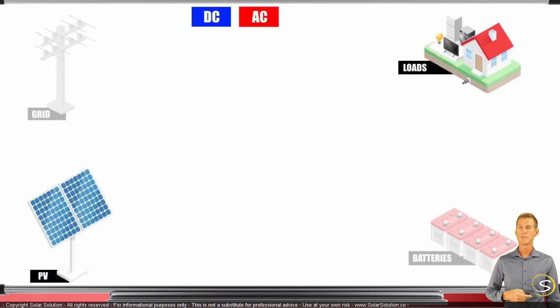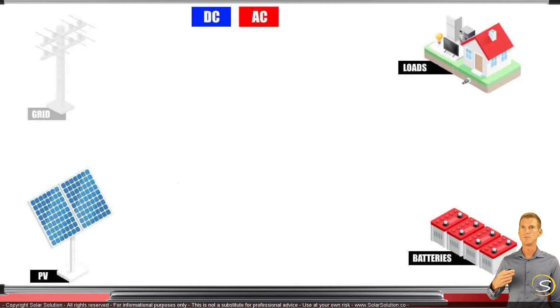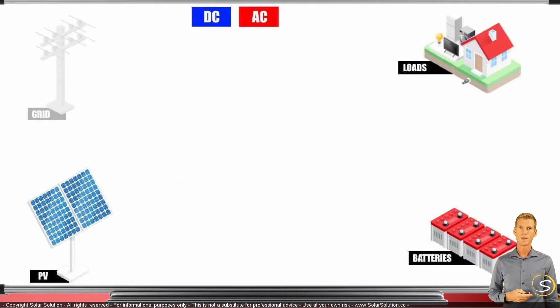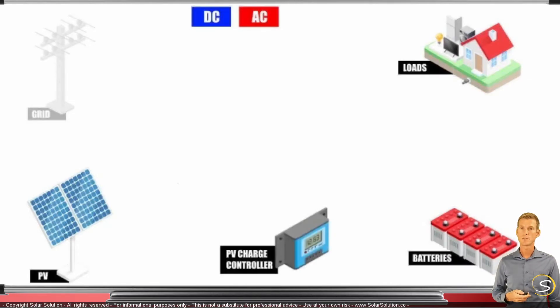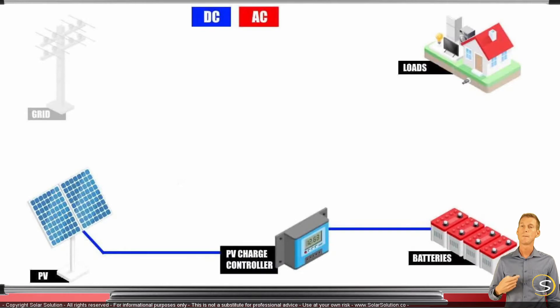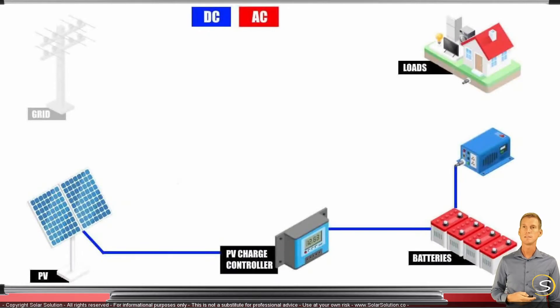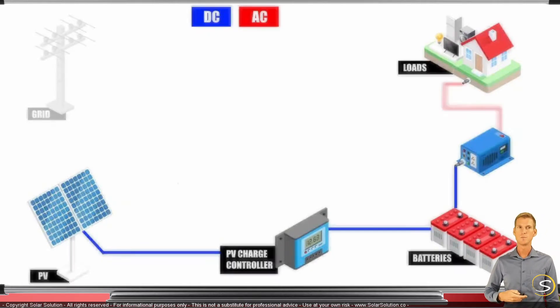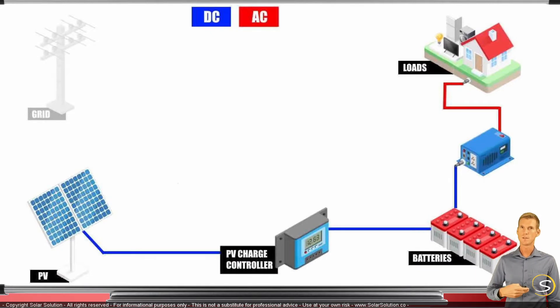In this off-grid scenario you would have batteries installed in your system, your solar array, and you're consuming electricity in your house through your loads. You would connect your solar panels through a DC-to-DC solar charge controller — a PV charge controller — to your batteries. Then you connect your batteries through an inverter that converts DC to AC into your house. This would be an off-grid solar energy system with battery energy storage.